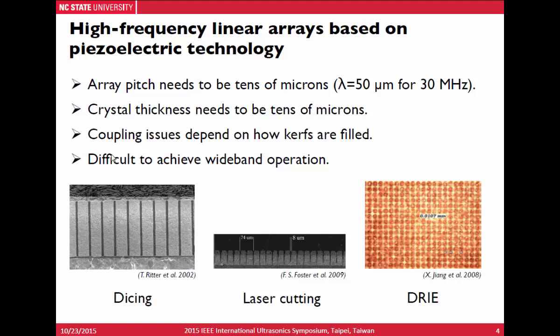Additionally, increased coupling could be observed depending on how the kerfs are filled. And finally, it is difficult to achieve wideband operation for piezoelectric transducers.